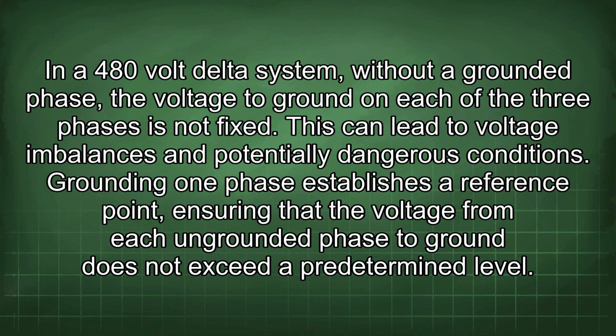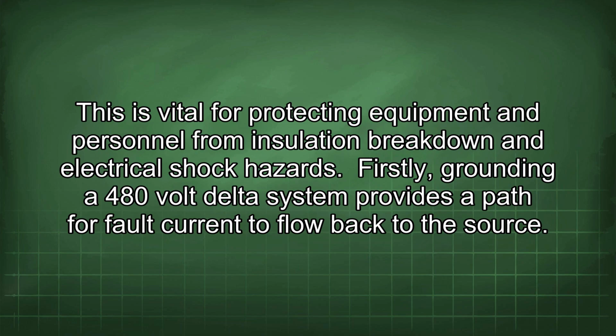Grounding one phase establishes a reference point, ensuring that the voltage from each ungrounded phase to ground does not exceed a predetermined level. This is vital for protecting equipment and personnel from insulation breakdown and electrical shock hazards.